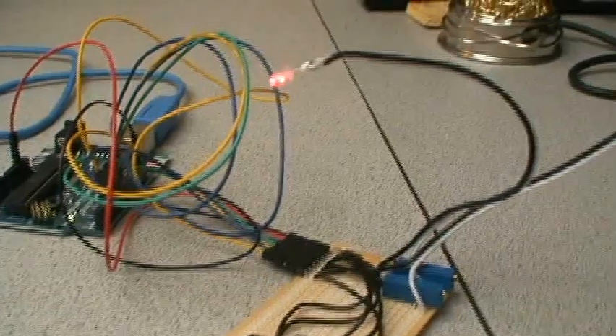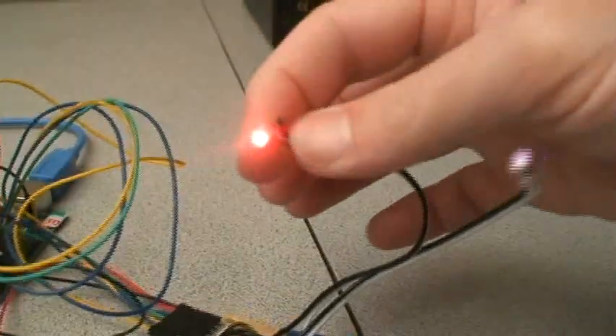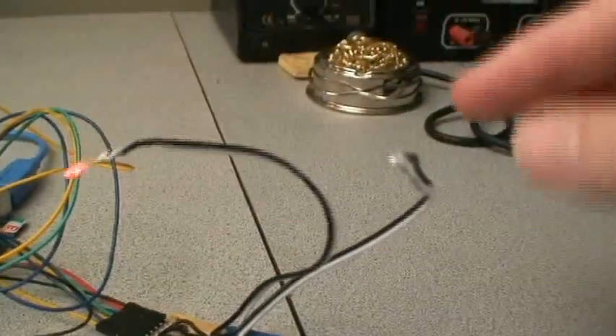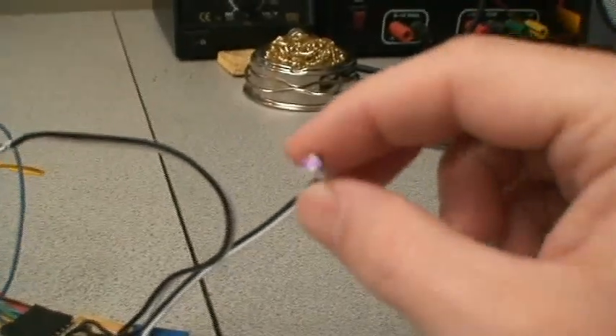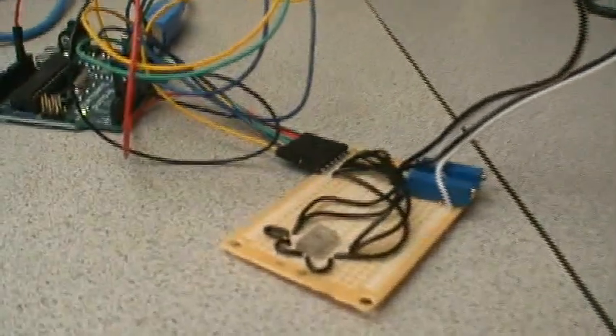And so when we turn on the red LED, the light that's absorbed from measuring the red LED is the oxygen-rich red blood. The infrared LED doesn't care about the oxygen-rich blood, so we use that basically as a baseline. So we're going to compare the light that's absorbed from the infrared LED with the light that's absorbed with the red LED, and that will give us our oxygen saturation.